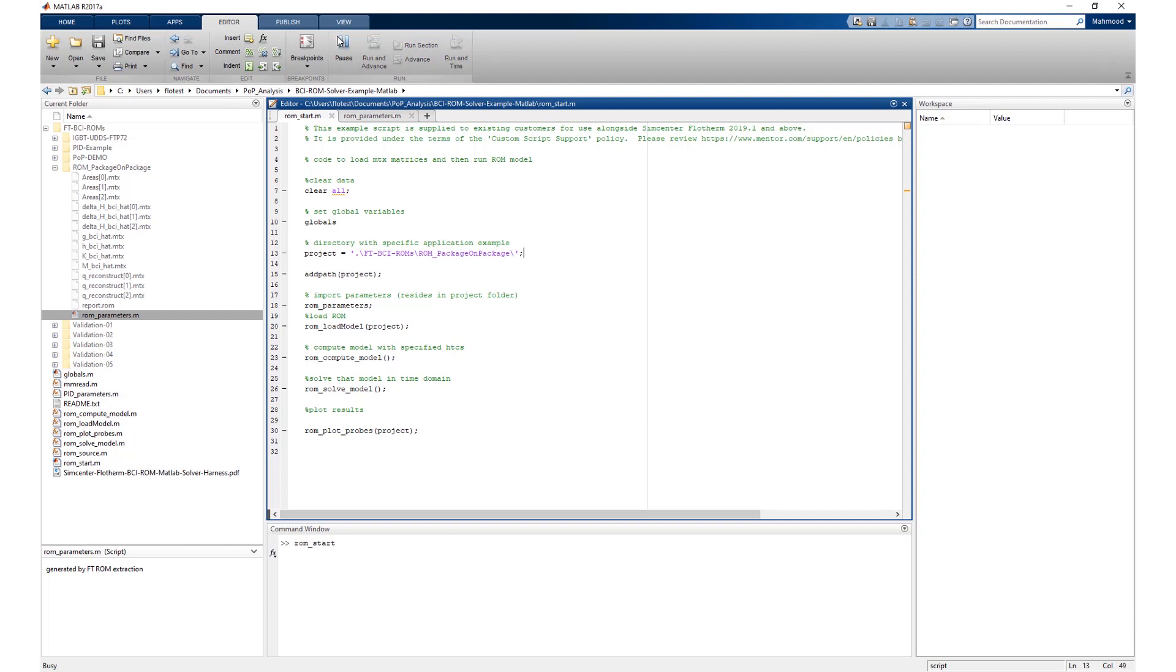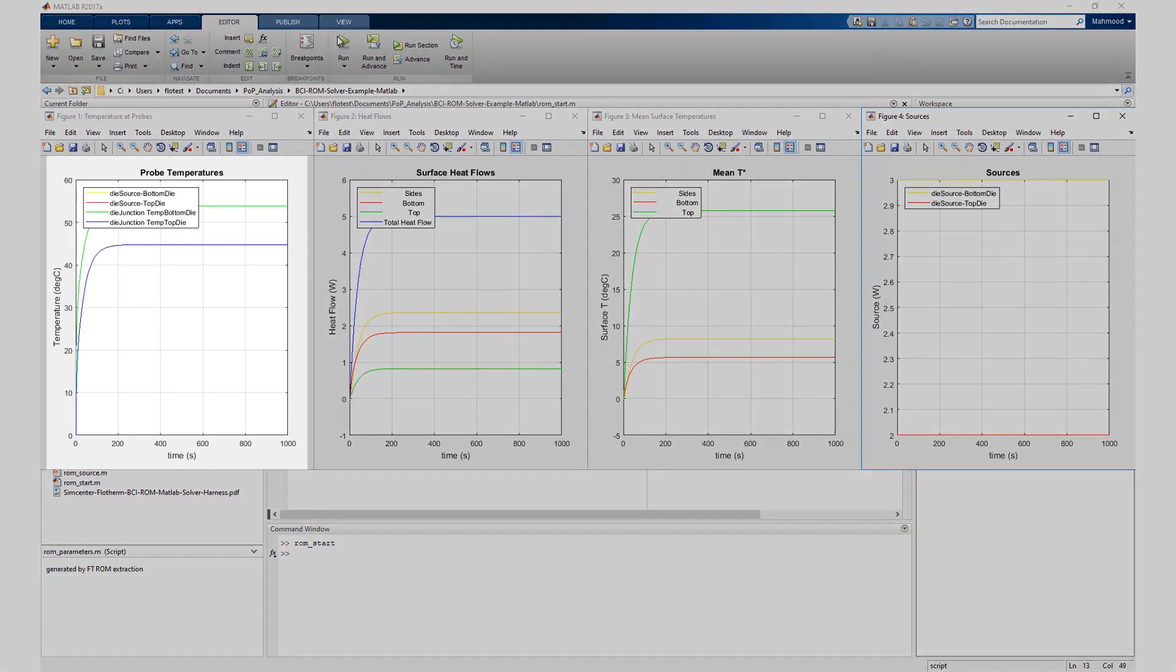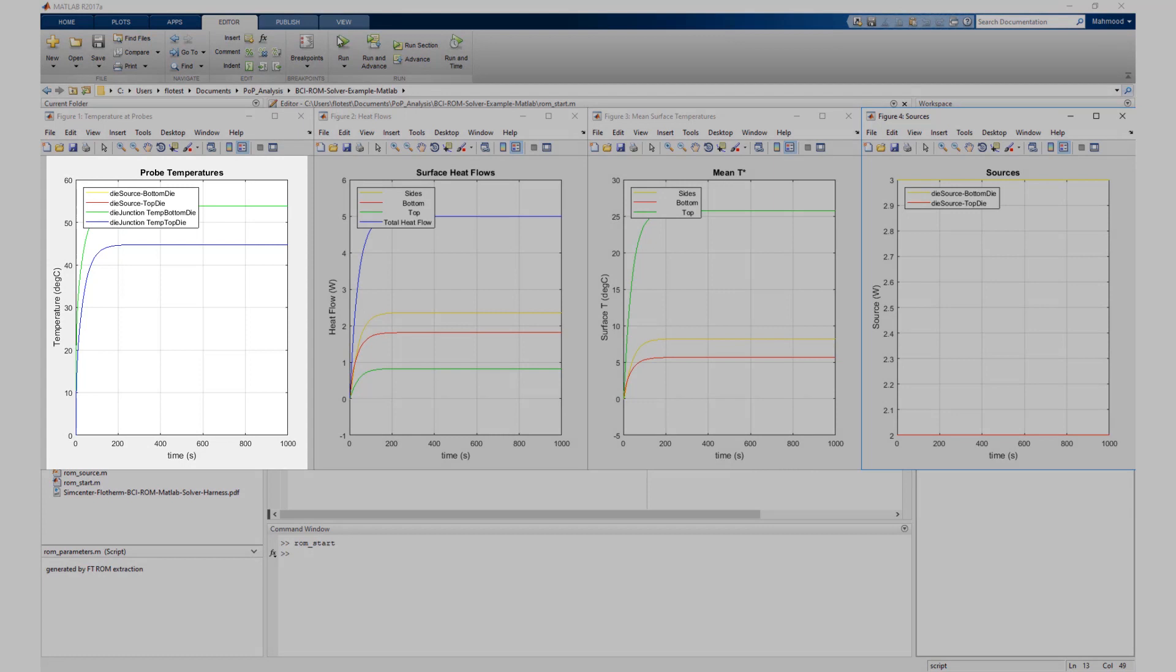The ROM solver harness is configured to create four charts by default following ROM solve completion. One: probe temperature versus time. The probe temperatures are centroid temperature for every heat source in the Simcenter Flotherm model, and temperatures for every monitor point in the Simcenter Flotherm model.